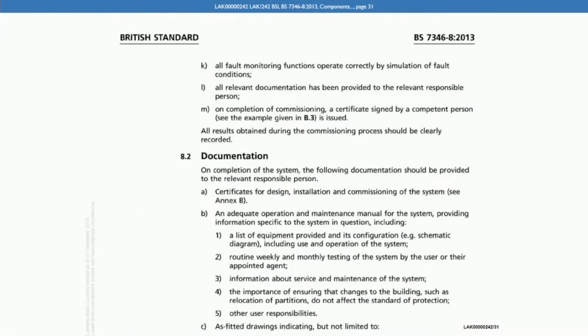sorry, we've just got that. After M, go back onto page 31. Yes, after M, we can see it says all results obtained during the commissioning process should be clearly recorded. Again, did you understand that? I understand it, but the results I recorded were the relevant results to door velocities, door force, and whether or not component parts operated correctly, i.e. dampers opening and closing, etc. Yes. So all the items listed on the commissioning sheet is what I believe are relevant to the commissioning process.